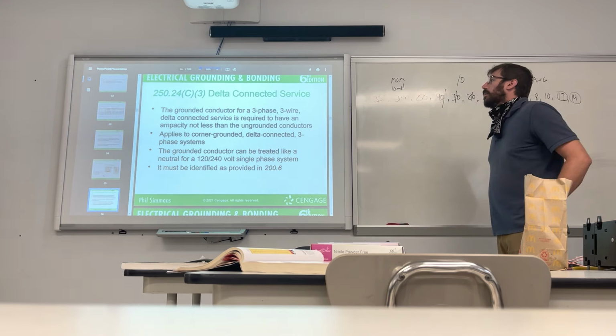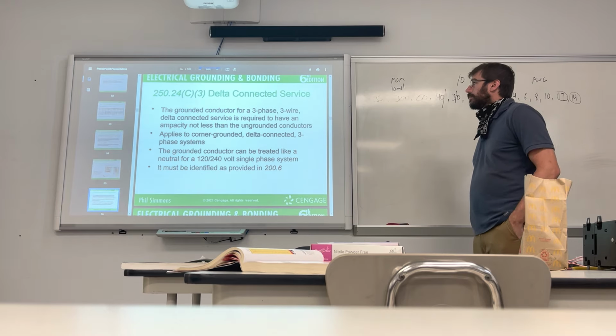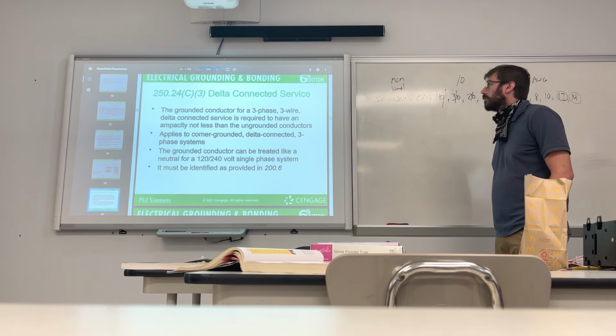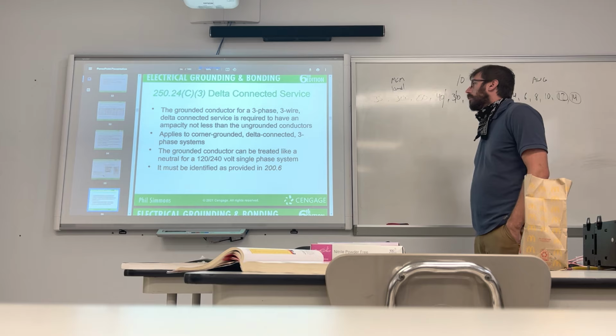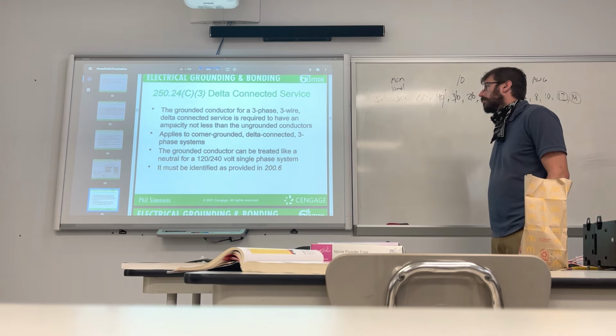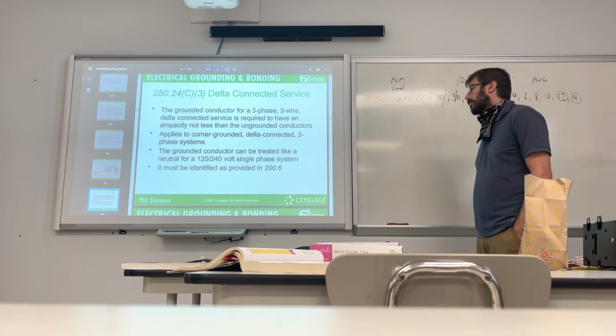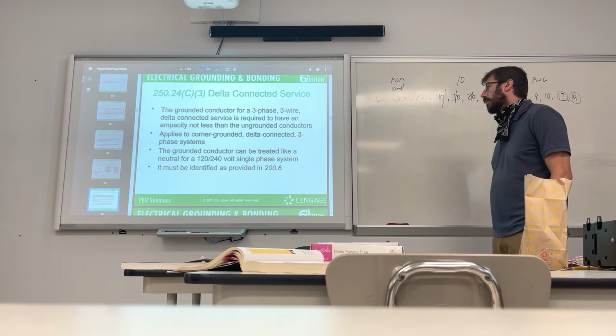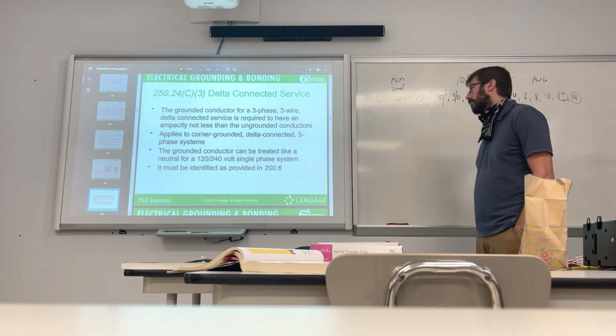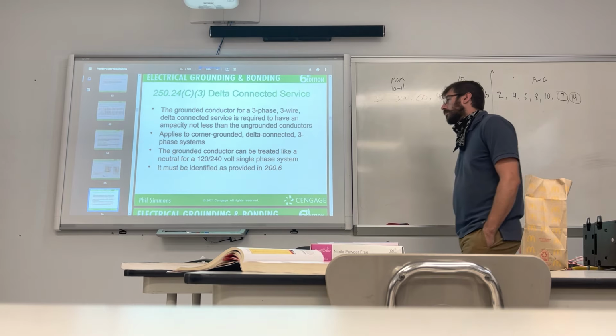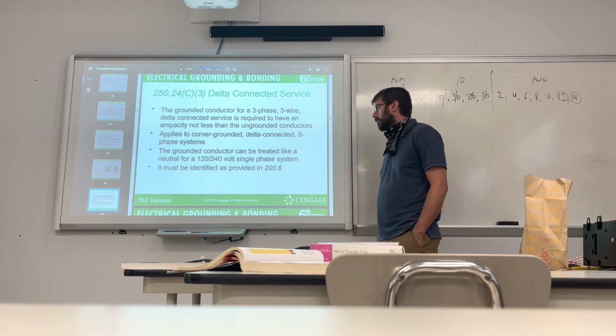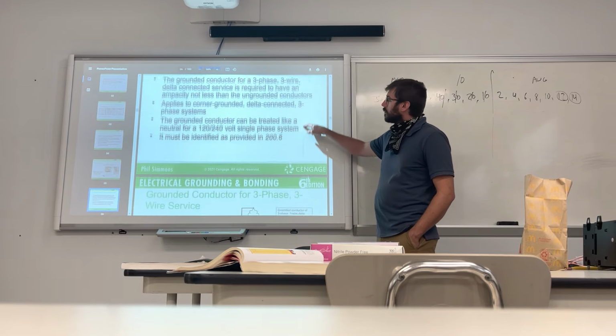250.24(C)(3) Delta Connected Services. The grounded conductor for a 3-phase, 3-wire delta connected service is required to have an ampacity not less than the ungrounded conductors. This applies to corner-grounded delta connected three-phase systems. The grounded conductor can be treated like a neutral on a 120/240 volt single-phase system and must be identified as provided in 200.6.